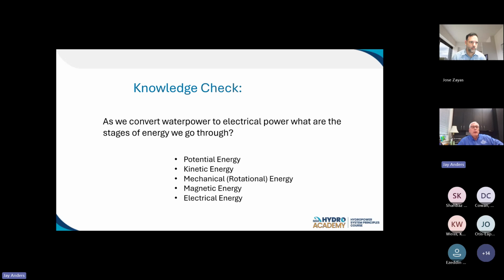We've talked an awful lot thus far about potential to kinetic, to magnetic, to mechanic. And finally, that mechanic really gets that rotor, that rotating magnetic field, rotating. We can do that many different ways. We're talking hydro specifically today, but as far as the generator goes, it doesn't really care what the prime mover is. Our prime mover today is water going against a turbine, moving it. We could have steam, we could have gas, steam from a nuke plant, a coal plant, whatever - we've got to get that relative motion between the rotating field, i.e. the rotor, and the stationary field, the stator winding.